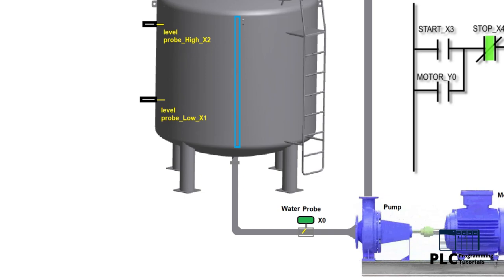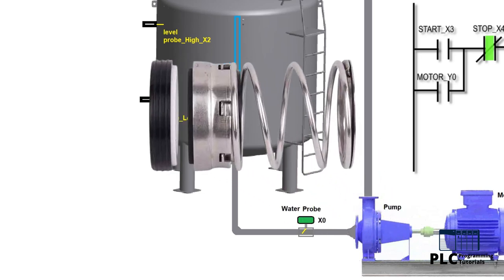Air bubbles get formed inside the pump and stop water pumping. If one continues to run without water in its impeller, its carbon shaft seals get hot because of the friction and get cracked, causing water leakage.